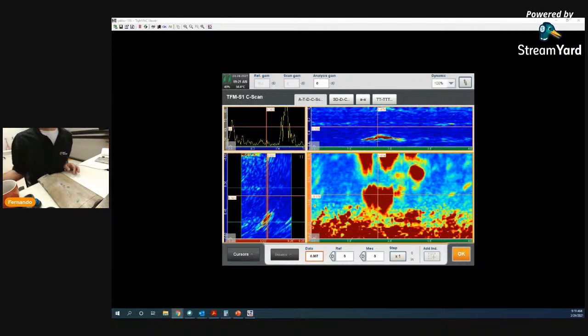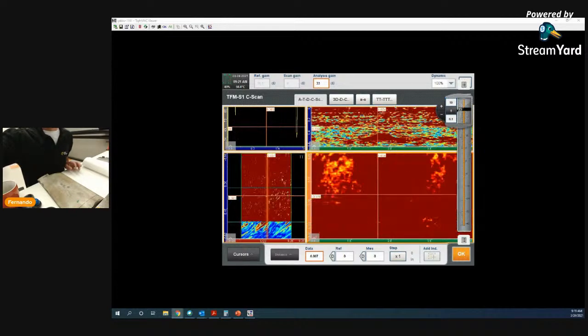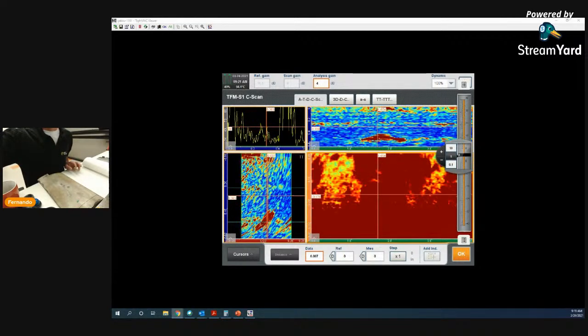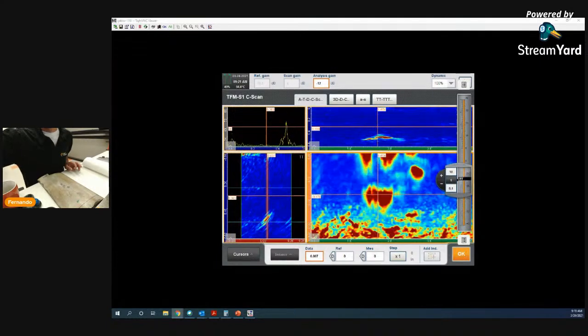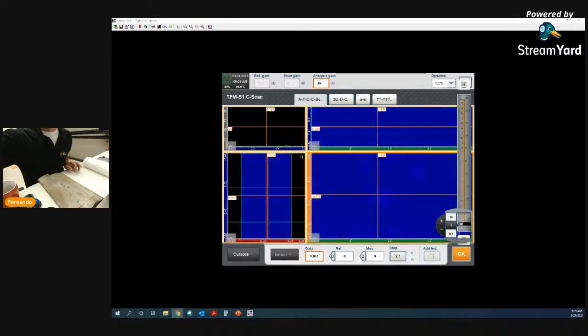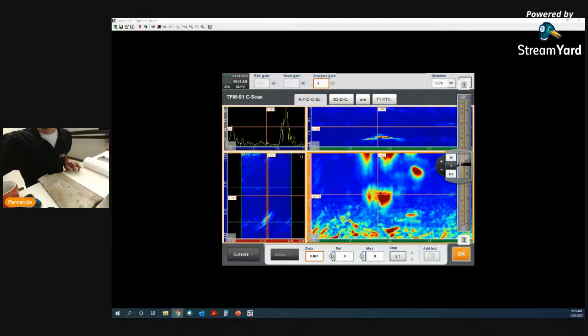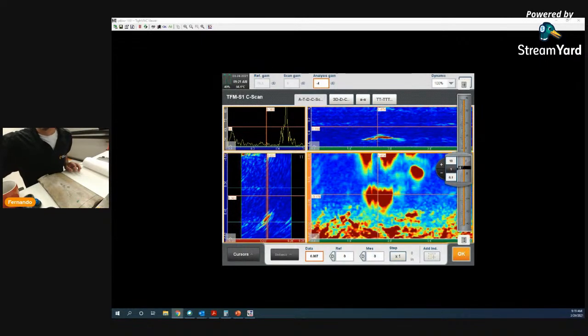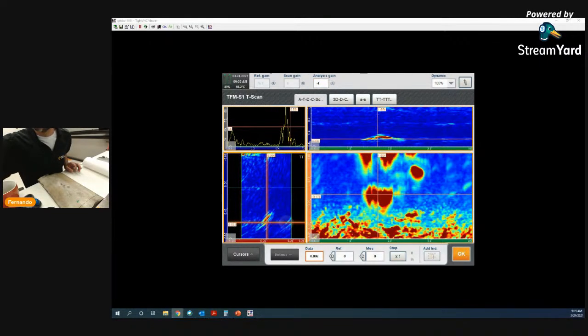Right now the gain was 76 dB, right? One thing I have on the equipment is the ability to increase it by up to 40. Now if a signal is saturated, one thing I can do is drop it. See that? You can decrease it minus 20, or minus 40 maximum. My thickness was a 1/4 inch, right?